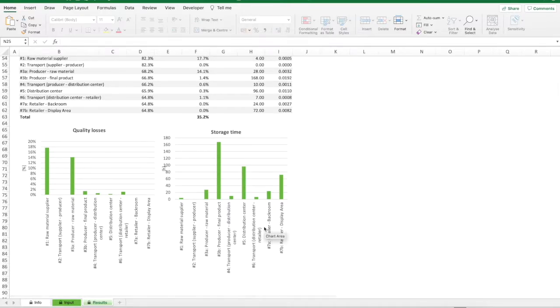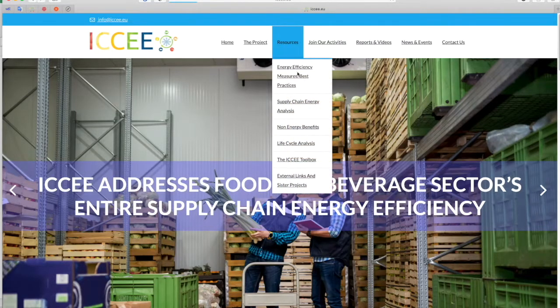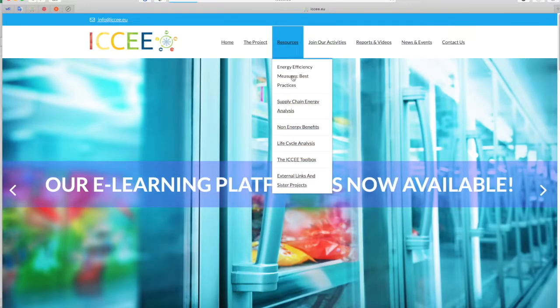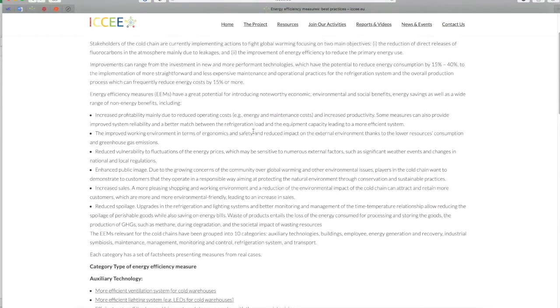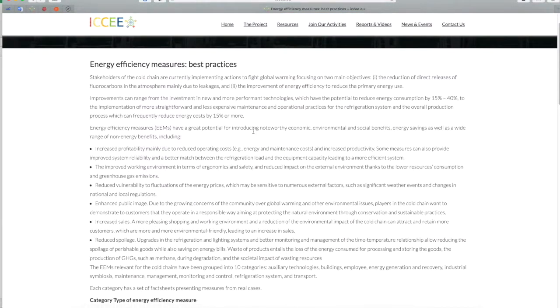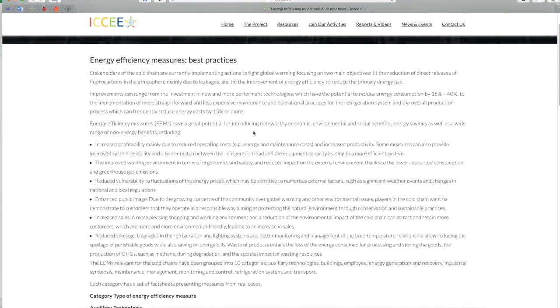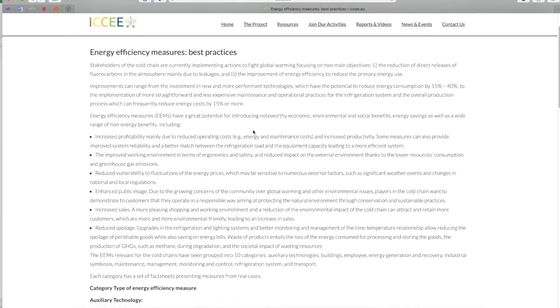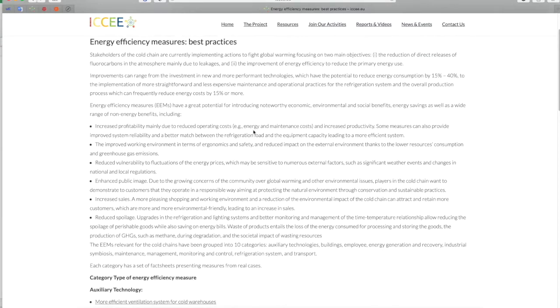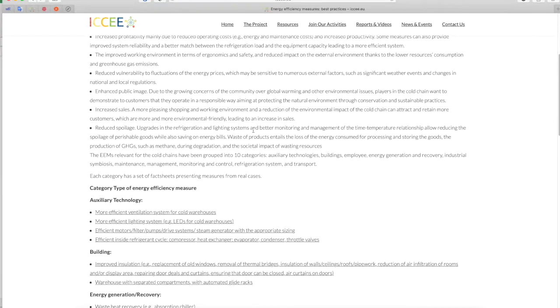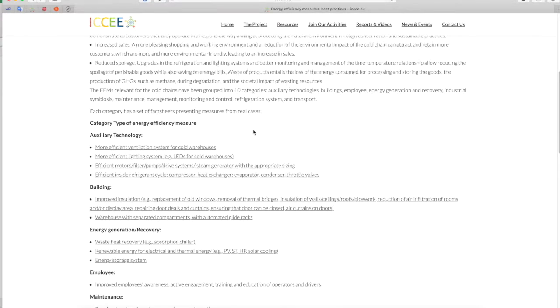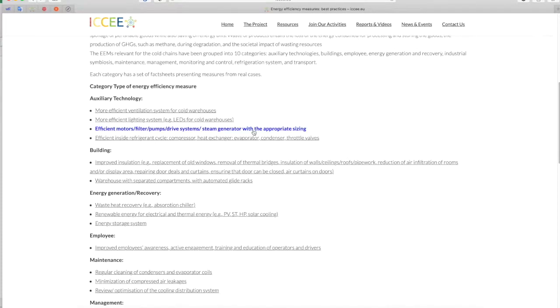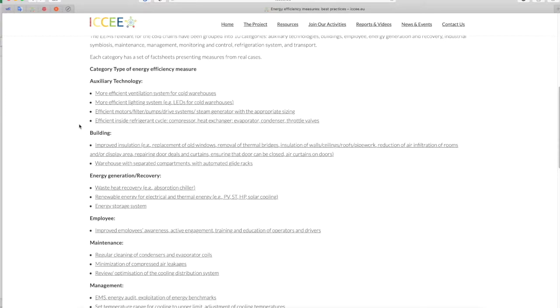On the website, specifically in the resources section, energy efficiency measures best practices, it is possible to have a look on the most relevant interventions for the food and beverage industry. Improvements can range from the investment in new and more performant technologies, which have the potential to reduce energy consumption by 15% to 40%, to the implementation of more straightforward and less expensive maintenance and operational practices for the refrigeration system and the overall production process which can frequently reduce energy costs by 15% or more.